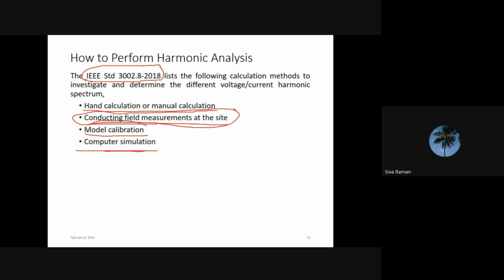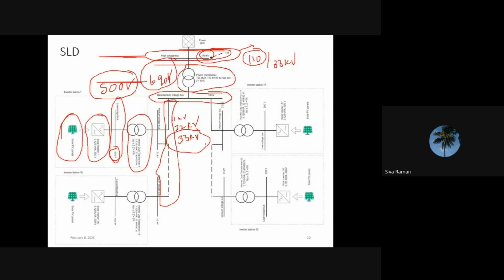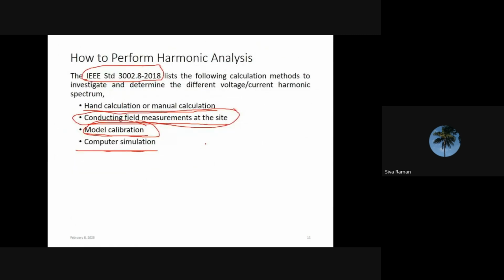Model calibration means we can simplify our model. For example, the entire solar plant model in a simulation software, we can perform the harmonic analysis, and we can design mitigation devices also. So this is called model calibration. Generally, this kind of model calibration will be done during the harmonic filter design stage.